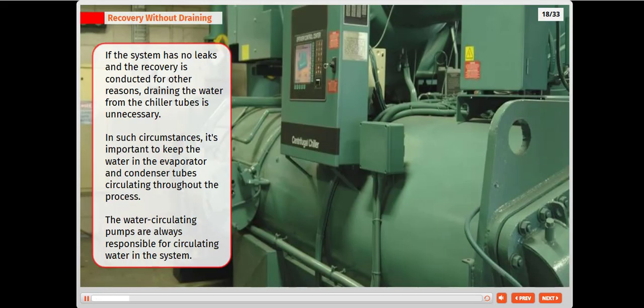If the system has no leaks and the recovery is conducted for other reasons, draining the water from the chiller tubes is unnecessary. In such circumstances, it's important to keep the water in the evaporator and condenser tubes circulating throughout the process. The water circulating pumps are always responsible for circulating water in the system.